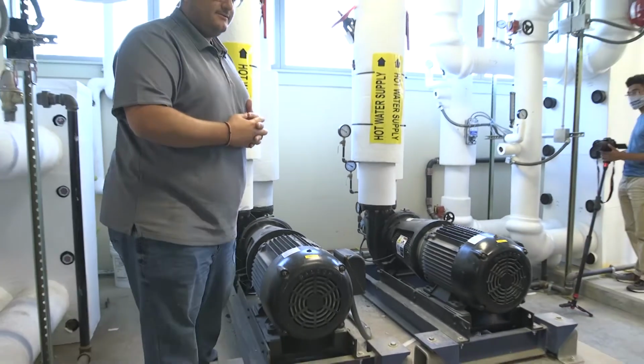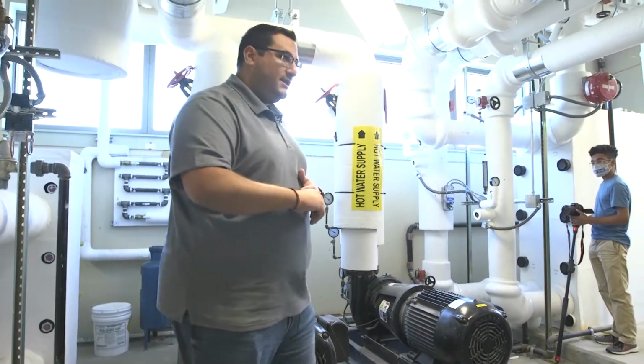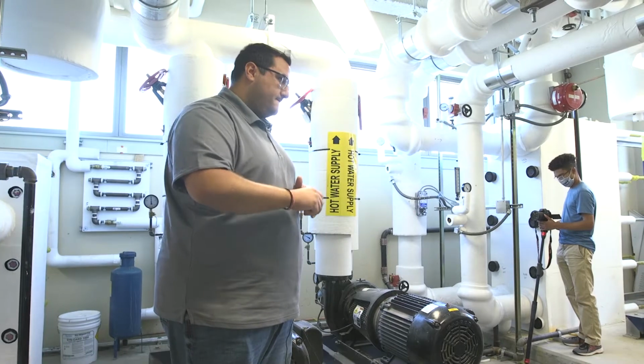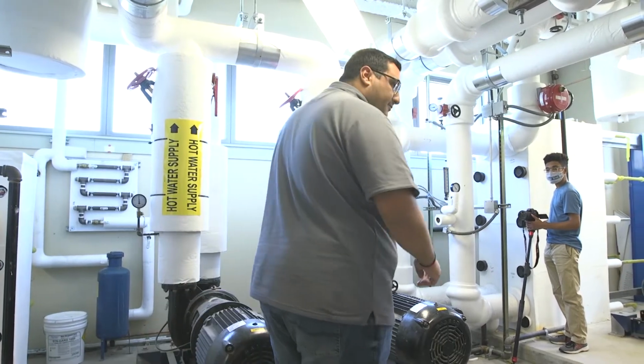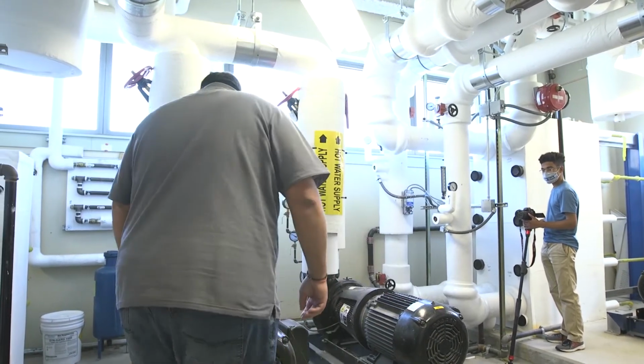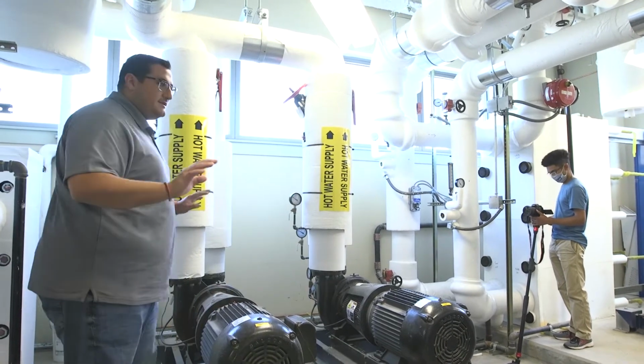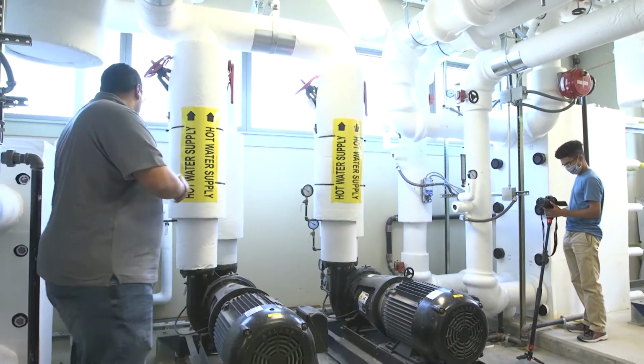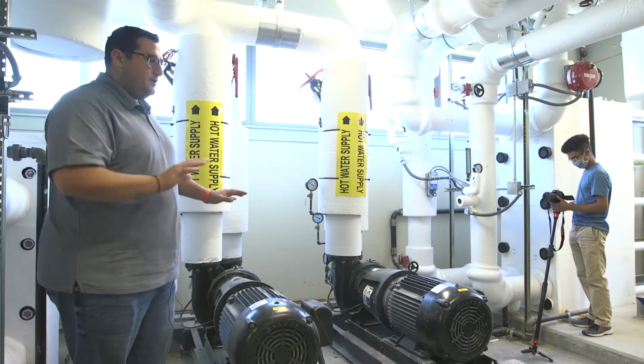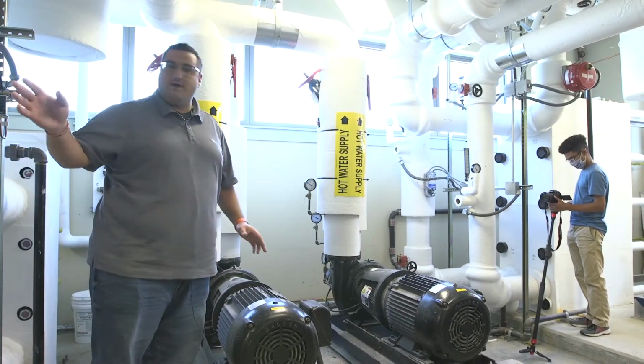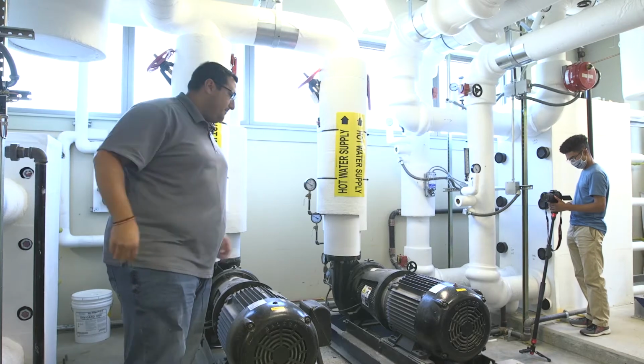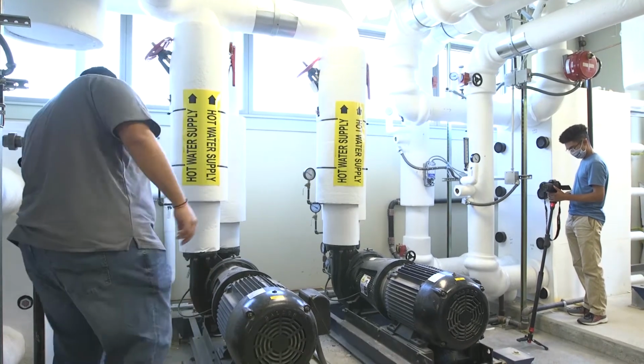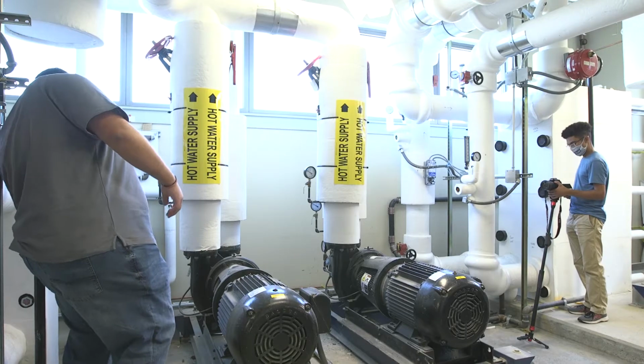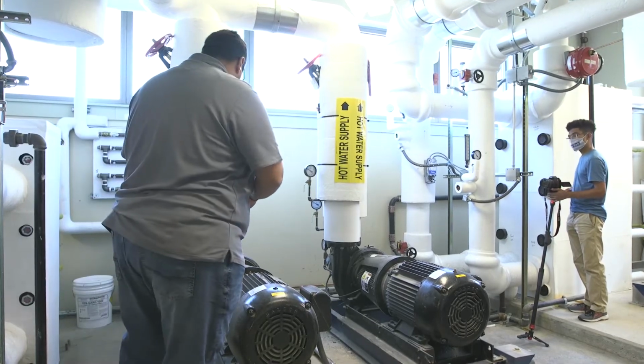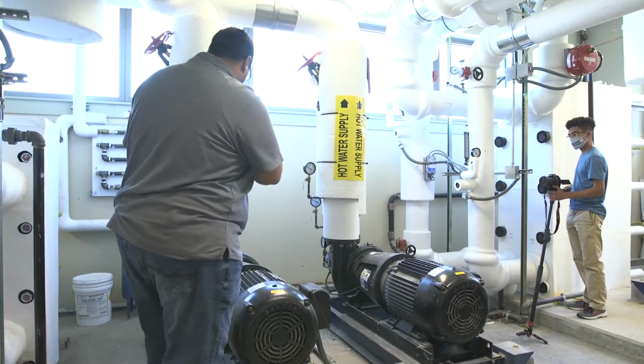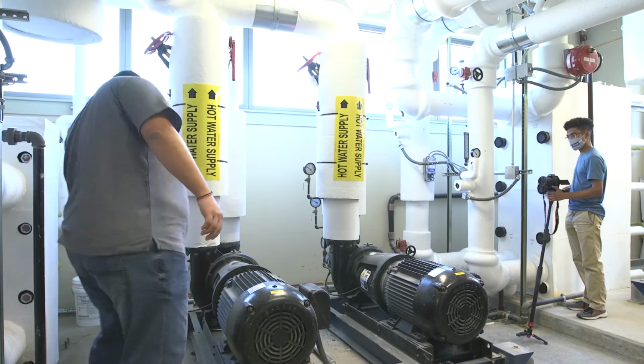Are you guys good with that? Any questions on that so far? This pump's on right now, right? Yeah. And that pressure was supposed to be right on the supply. I don't know what the system calls for, but you can look at the two gauges and you see that the pump is pumping, but I don't know what your system needs to be doing. I think these are on VFDs. They're controlled separately, whatever, but it's on. And it should be rotating counterclockwise. You should be fine with that.